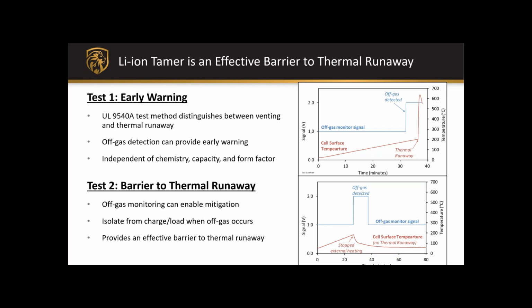The second test is designed to show how this can also be used as a barrier to thermal runaway. We heated the cell the same way, but this time when off-gas detection indicated the cell had vented, we turned off the abuse and let the cell cool back to room temperature—showing it was not in thermal runaway at the time of the off-gas event. This demonstrates off-gas detection as an effective barrier to help prevent thermal runaway in lithium-ion battery systems.